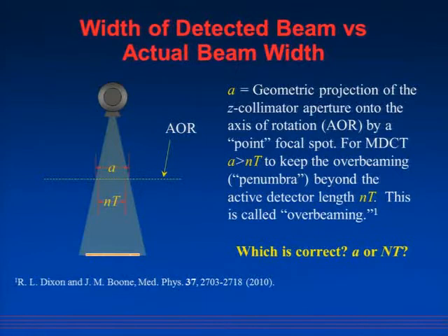I don't want to leave anybody out, but I know GE has a term, if you were the technologist setting things up, called efficiency, and this is what they're referring to. You will know that the efficiency is usually 90-something percent. But if you go down to a narrow beam width, you'll see that the efficiency will go down to 50-ish percent.